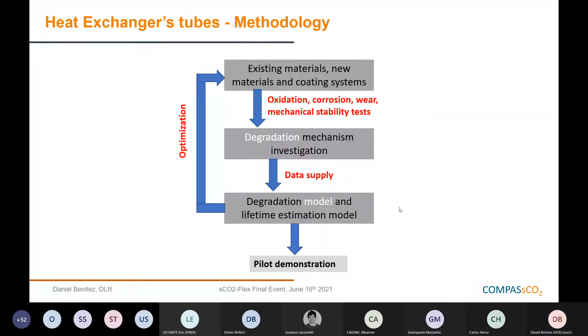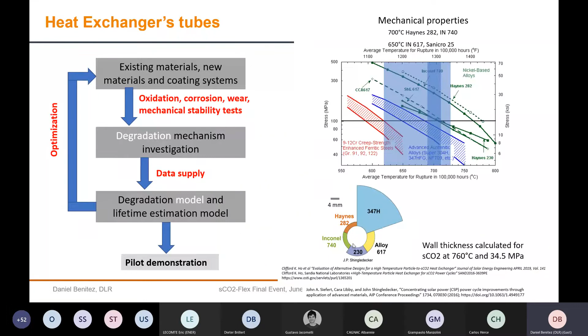We also noticed that depending on the material, we will have a different wall thickness, and this is very important for the heat transfer coefficient in the heat exchanger. This is an iterative process: if we select a material that requires too thick a wall, the heat transfer is not so good, so the temperature rises on the outside, and then we need more tubes, increasing the cost. So this is an iterative optimization process we are following.